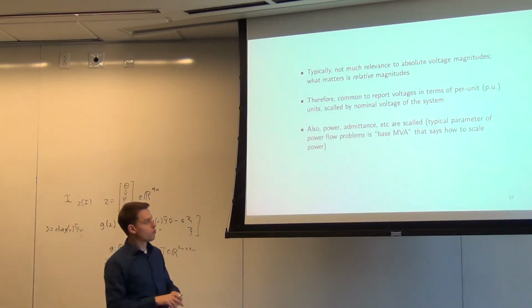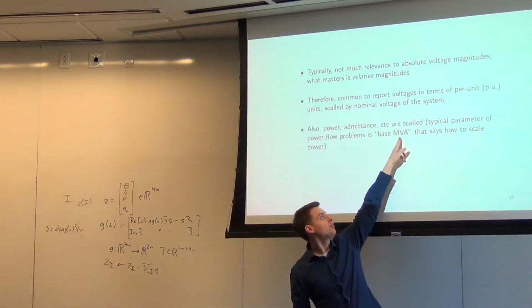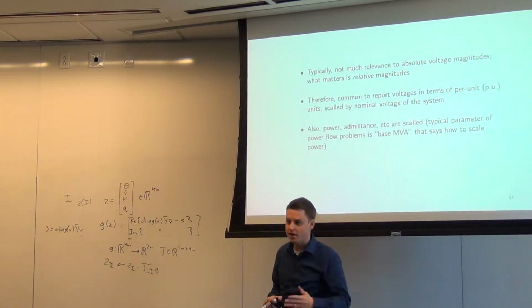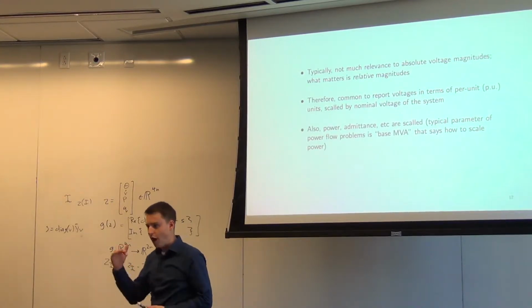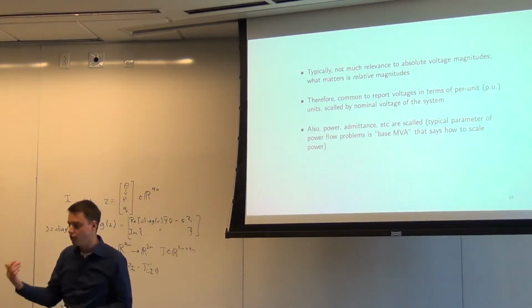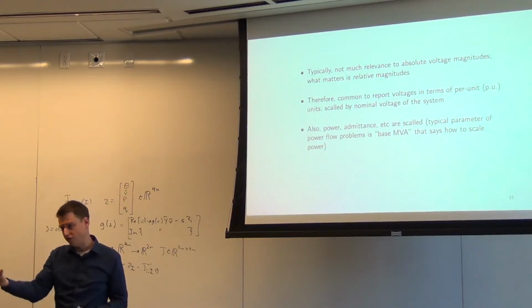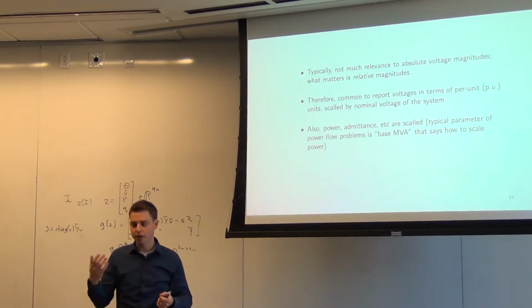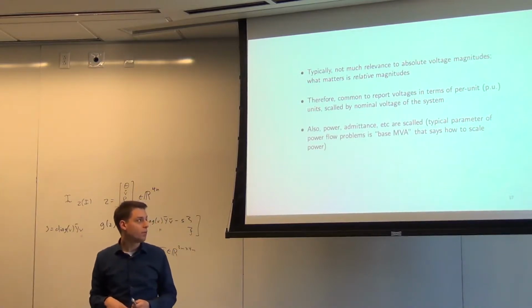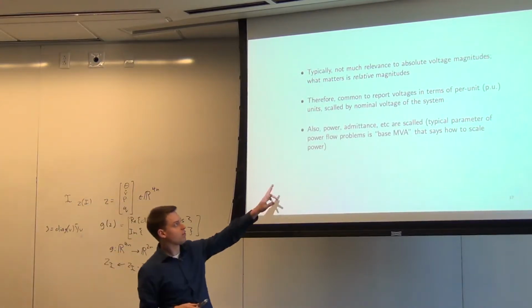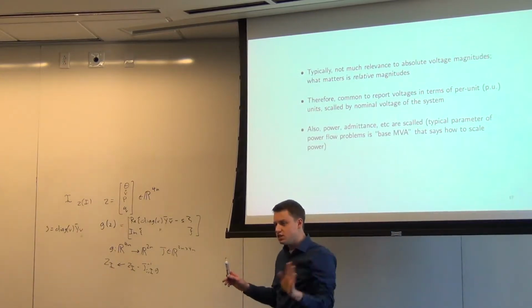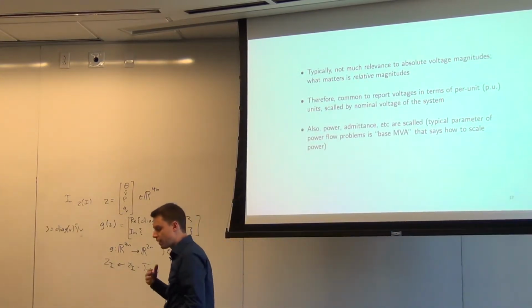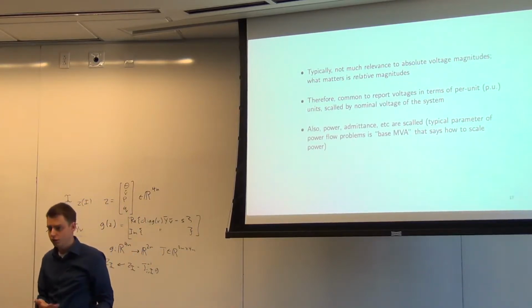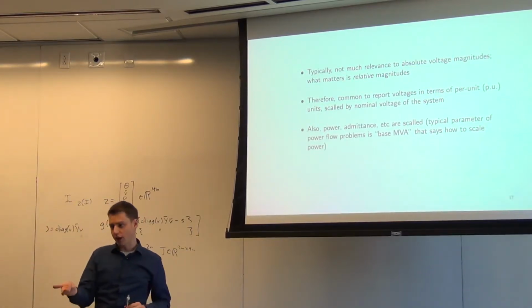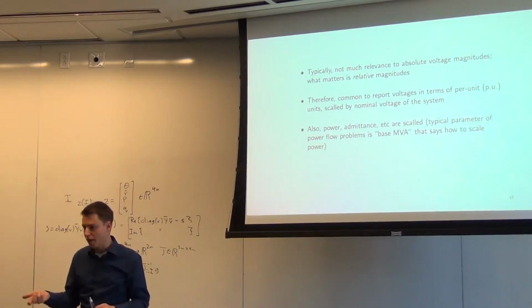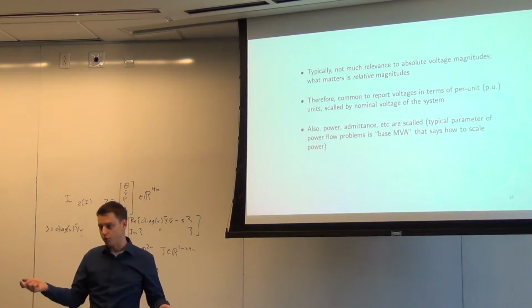So typically we scale all the quantities by a quantity called the base megavolt-amperes, or base MVA. Most power flow files will tell you what the base MVA is and give you power quantities relative to that. So you scale voltage by these PUs and scale power by this base MVA. Power is also sometimes called PU when scaled this way, but the simple point is that in real power flow you'll see these things all scaled to a certain amount — just be aware of that. You're not talking about raw, absolute megawatts or absolute kilovolts.